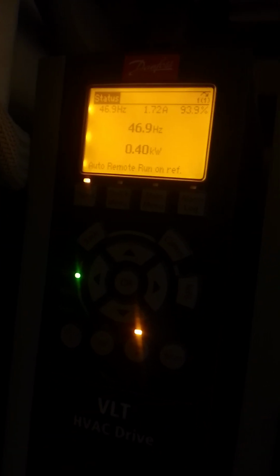This is the HVAC, a very small one. You can see this one. The current is running, I don't know whether you can see it, at 1.66 amperes with 46.8 hertz, 0.33 kilowatt. It's a very small motor. It's a small motor, not very small. Though it's not that small because it is 5 horsepower, but the demand is not that high, so it will adjust the speed according to the demand.